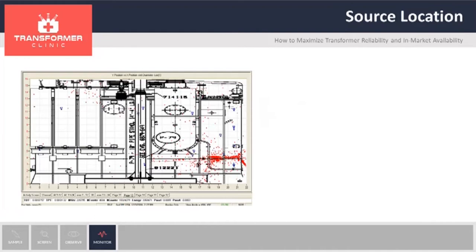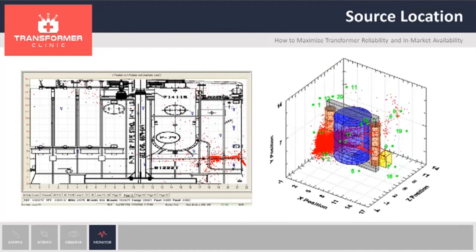At the end of monitoring, you get something like this. One representation is two dimensions, where we can actually overlay the drawing of the transformer. If there is an active fault, it will be shown as a red dot. If you have a concentration of dots, we call that a cluster — that is typically a fault located on the transformer. In this case, you can see it's on the lower right corner. The other representation is a three-dimensional location where you can see the coil and the core, with red dots indicating the fault.